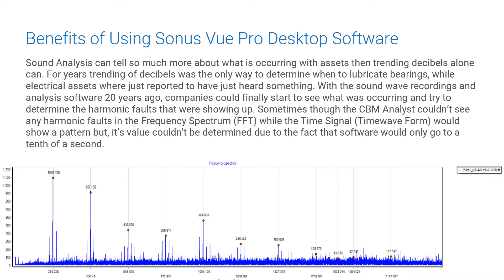Sound analysis can tell so much more about what is occurring with assets than trending decibels alone. For years, trending in decibels was the only way to determine when to lubricate a bearing, while electrical assets were just reported as having heard something. With sound wave recordings and analysis software available about 20 years ago, companies could finally start to see what was occurring and try to determine the harmonic faults that were showing up.